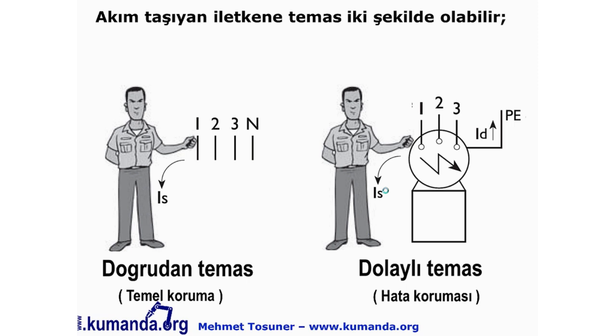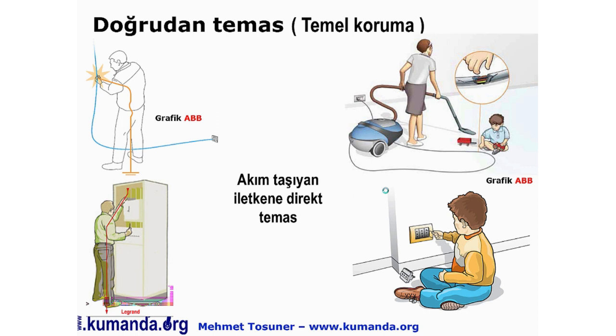Önce bazı tanımlarla başlayayım. Akım taşıyan iletkene temas iki şekilde olabilir: ya doğrudan temas ya da dolaylı temas şeklinde. Bundan sonraki literatürde doğrudan temas karşımıza temel koruma, dolaylı temas ise hata koruması şeklinde gelecek. Doğrudan temas — temel koruma — akım taşıyan iletkene direkt temas şeklinde olur; bir pano içerisinde ya da yalıtkanı gitmiş olan bir iletkene veya baraya direkt temas olabilir.